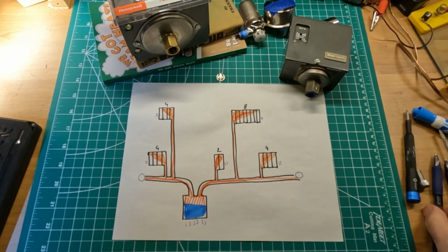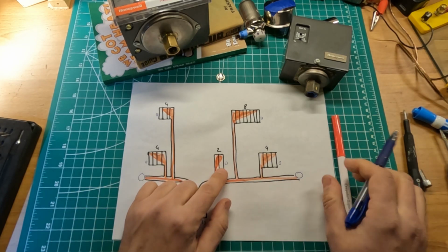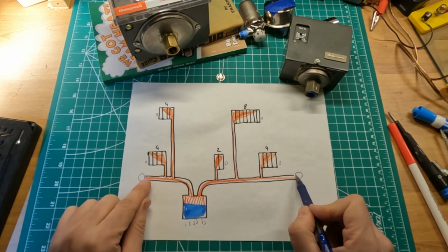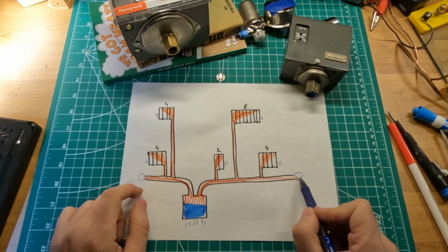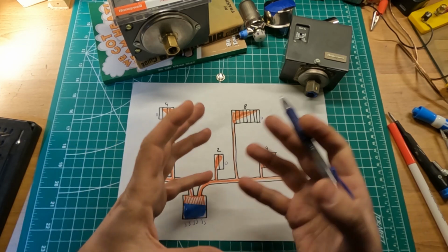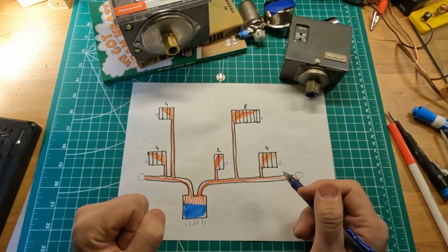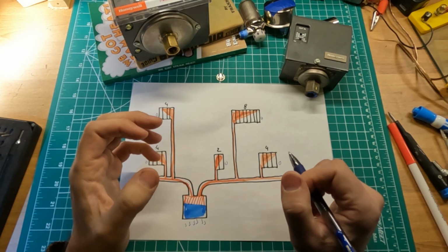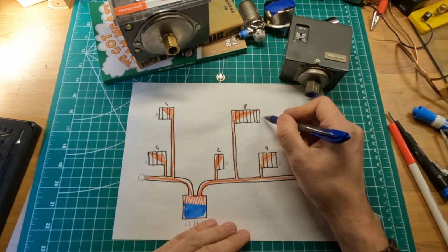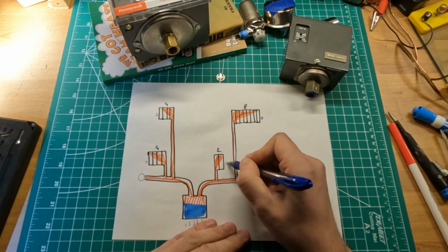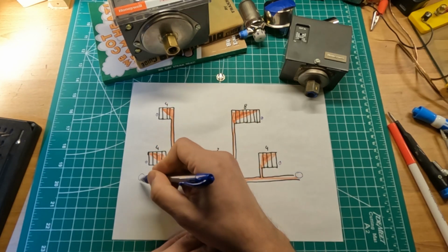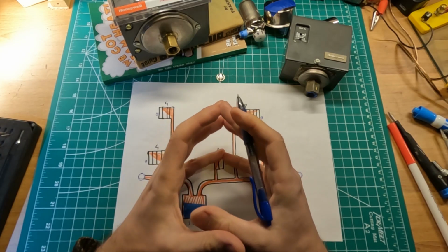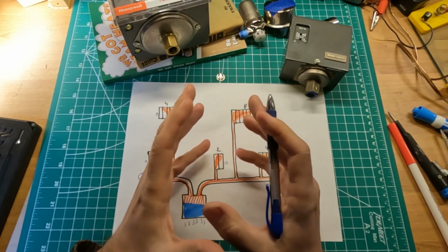Anyway, it doesn't matter. Then the steam hits those air vents on the radiators, and the vents on the end of the mains. By the function of the vents, they're supposed to close and trap the steam inside when they are exposed to steam. So all of a sudden, this vent closes, this vent closes, this vent closes, and also this main closes, this main closes. And the idea is that it stays closed as long as it's surrounded by the hotness of the steam.